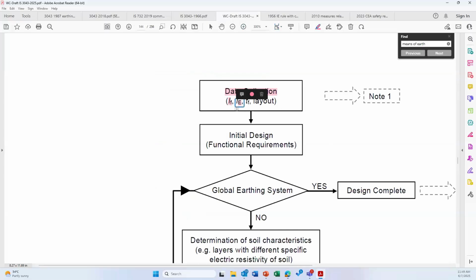Please note that the earth fault current may be of the order of 50 kiloampere. But IE, which is the current going to flow through the earth electrode, may be just a fraction of 50 kiloampere, maybe 500 amps or maybe 1 kiloampere, very, very small. TF is the disconnection time, and layout of this entire installation. This is the first data which you need to collect.